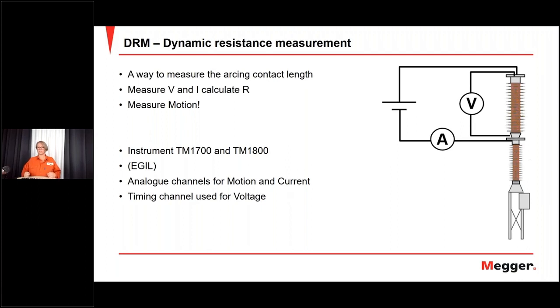To do this, you use a TM1700 or TM1800, and it can actually also be done with the EGIL. But the best solution, I would say, is to work with the big instruments here. You need analog channels for motion and current. And with TM1700 and 1800, we're using the timing channels to measure voltage. So we already have those circuits connected at the breaker. And you can connect this DRM set before you do the timing. So you can do all the connections at the pole directly.